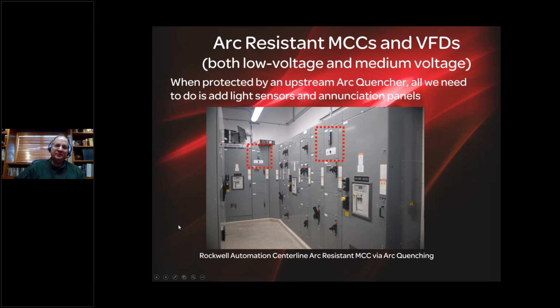The reason for that is, if you look at the red boxes I've just highlighted, we've had arc sensors installed, both fiber light sensors and point light sensors. Those tie into a sensor relay, because we don't want to wire all these sensors back individually to the upstream arc quencher and an annunciation panel. If you look closely, you can see that the blue LED is illuminated, indicating that the arc quencher system is active and working properly. The system, being a life safety system, runs multiple diagnostics per second on every single relay and sensor in the system. So by extending these sensors into the MCC, this motor control center becomes compliant with IEEE C37.20.7. It becomes arc resistant and is labeled as such.